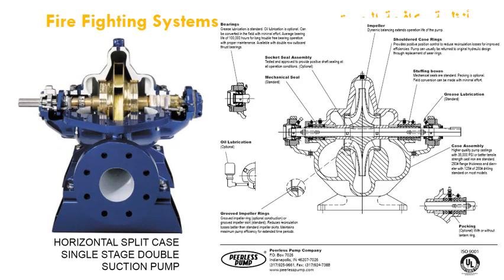This slide presents two diagrams. The first one on the left hand side is a photo cutaway for a horizontal split case single stage double suction pump. The shaft is affixed here horizontally with two bearings located here and here, and this is the end of the pump, and this is the discharge flange, and this is the impeller, which is affixed with both eyes of this impeller from both sides at the flow and the suction side divided on both sides of the impeller eyes. Then according to the rotational motion of the horizontal shaft, the impeller will rotate also and collect the water in the volute casing, which increases in this direction until it reaches the discharge flange of the pump as shown here.